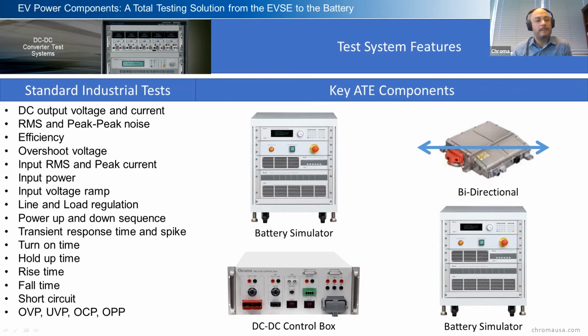Now, standard tests: you have to measure the output voltage and current, noise, efficiency, overshoot, undershoot, input current, power, and voltage ramp. So you want to ramp it up to a certain voltage and see what's your range of operation, because you can ramp it up, see when it turns on, go through your envelope, and then see where it shuts off if you're in an over-voltage type situation.